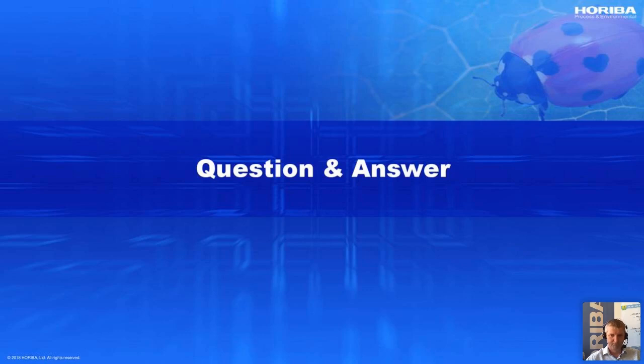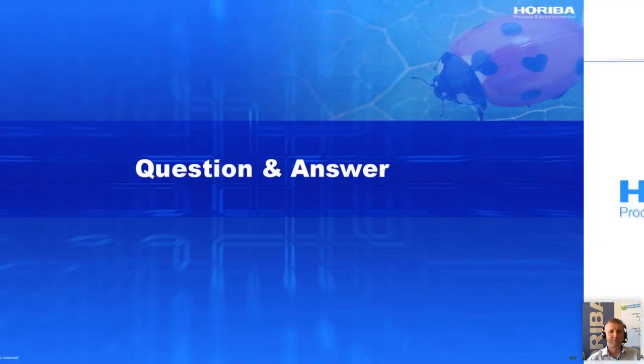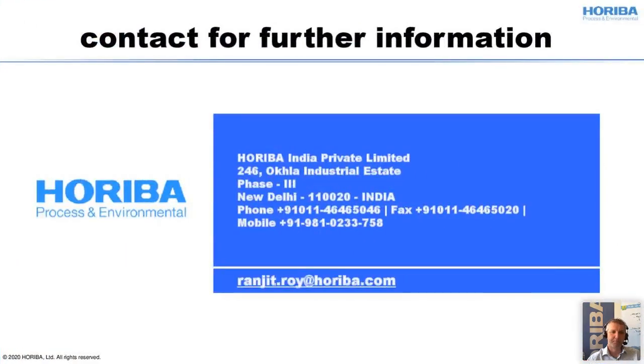The next question is, is the instrument flame-proof or not? No, for CEMS, you do not require any kind of flame-proof analyzers or instruments. But yes, if you are from an oil and gas industry or any kind of explosive industry, we can also give you flame-proof instruments to cater to your application.